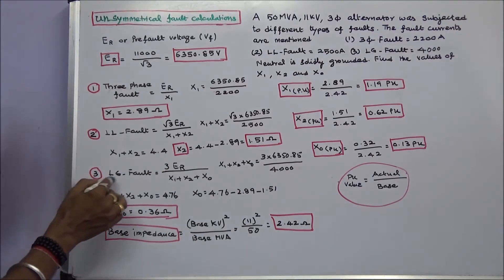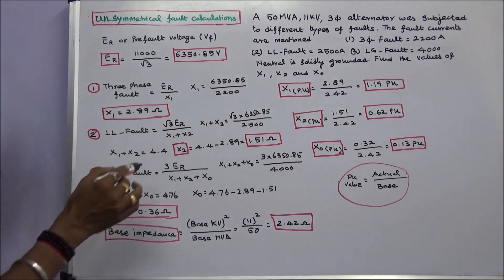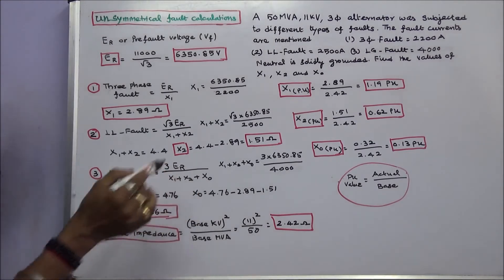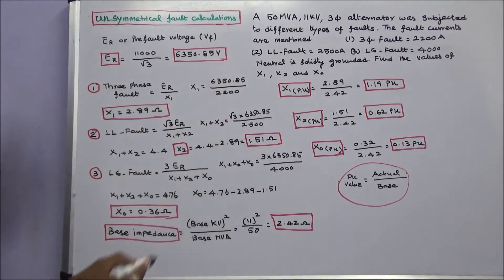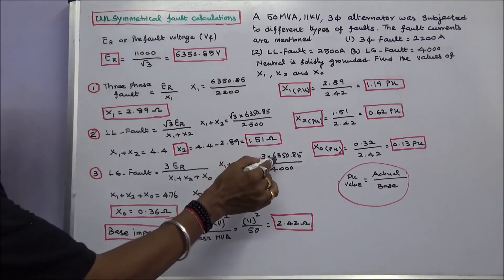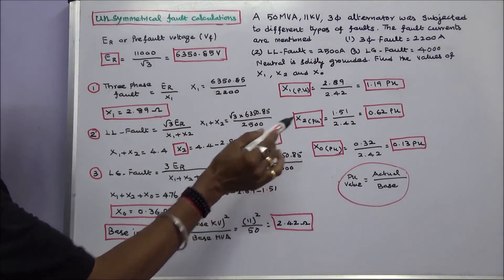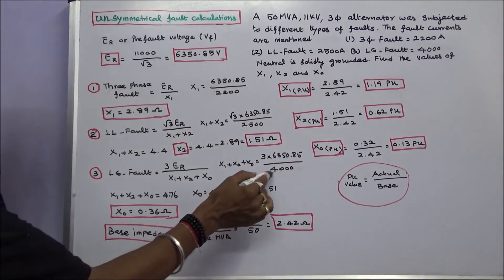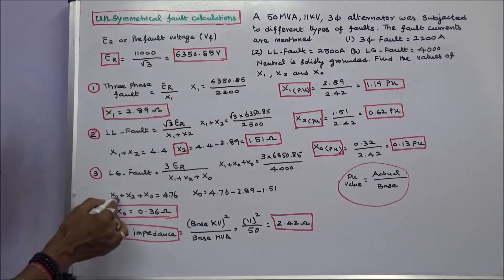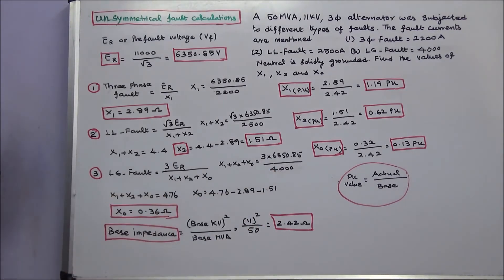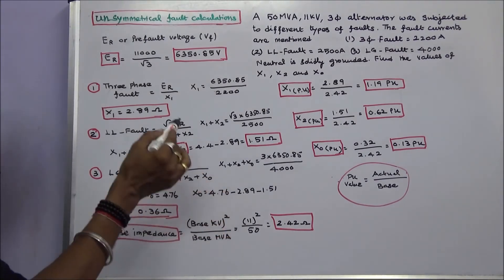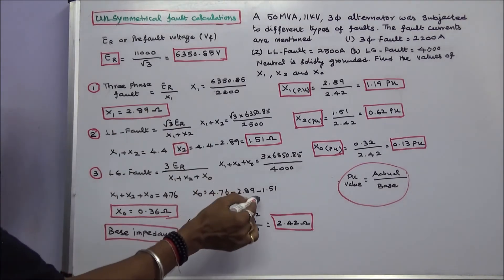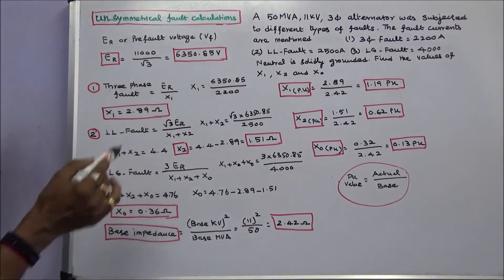The third case is the line-to-ground fault. The formula is 3 multiplied by ER divided by (X1 plus X2 plus X0). The current is given as 4000 amps. Therefore X1 plus X2 plus X0 equals 3 into 6350.85 divided by 4000, which gives 4.76 ohms. Therefore X0 equals 4.76 minus 2.89 minus 1.51, giving X0 equal to 0.36 ohms.